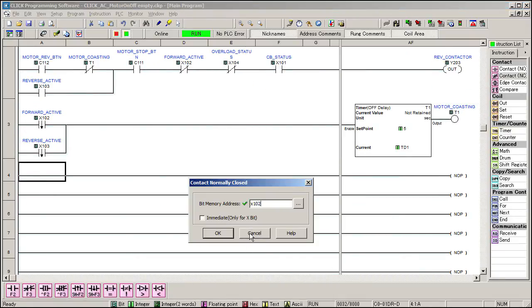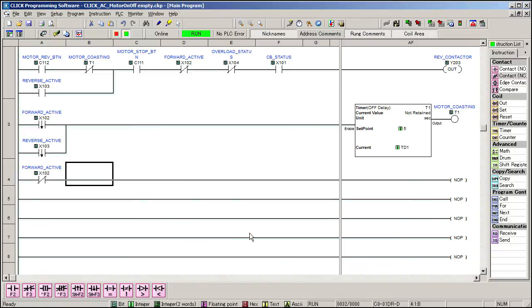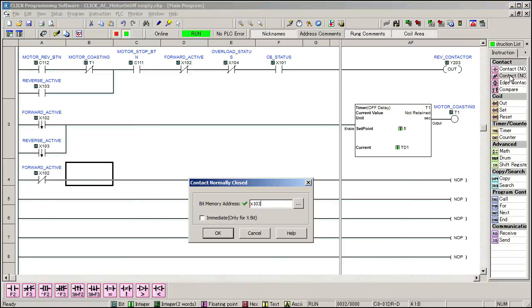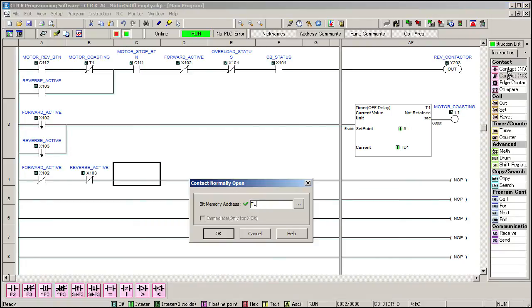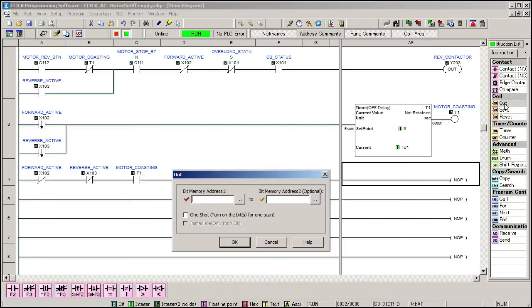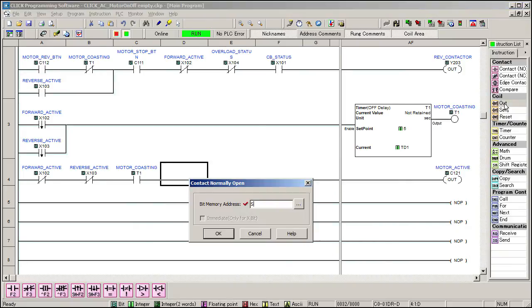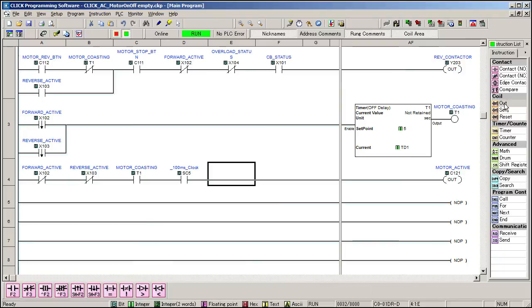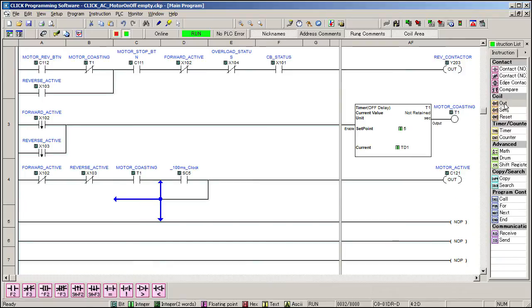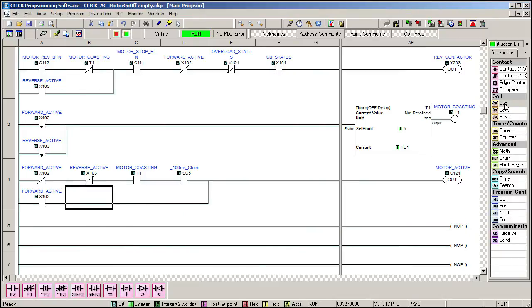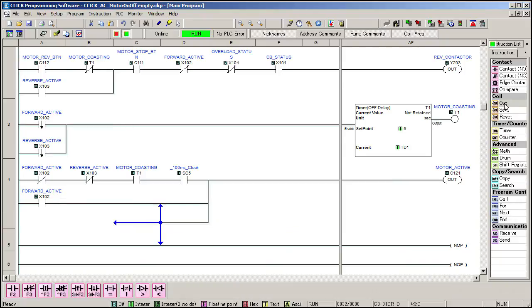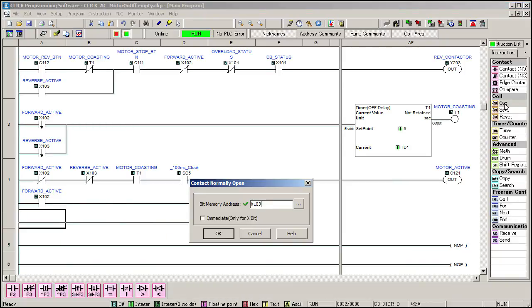If the reverse and the forward contactor are not active, but the motor is coasting, we'll set a bit to indicate that the motor is still active. If we add the system 100 millisecond bit here, it will make the light flash. This will drive the stop button indicator which is just the inverted version of this motor active bit. We also want to turn on the motor active bit if either contactor is active. Again this will turn off the stop button indicator.